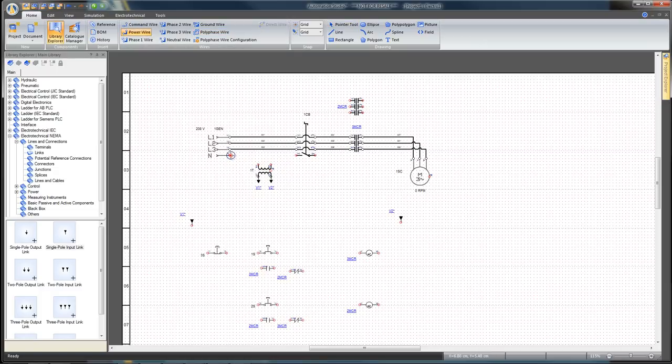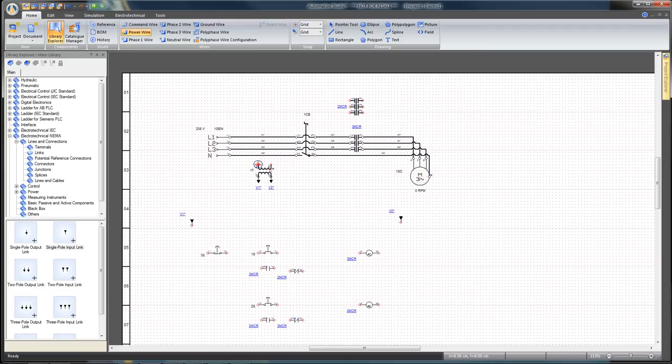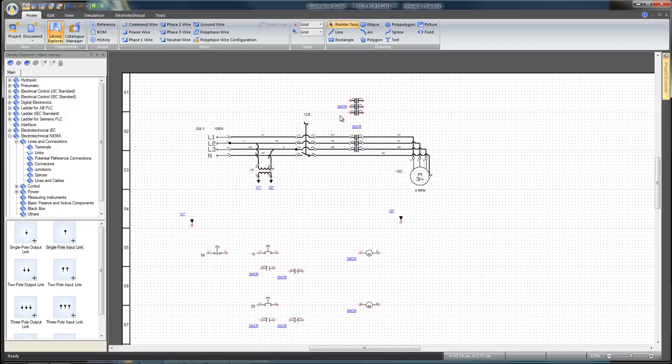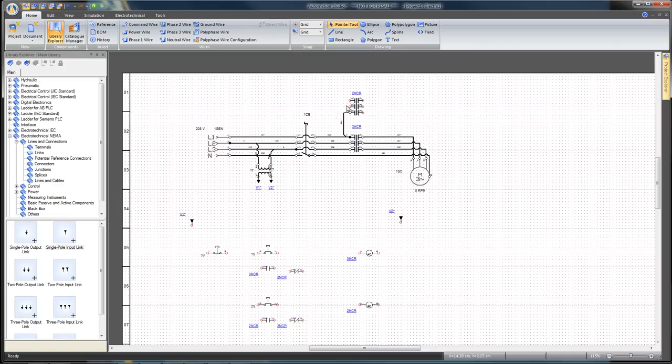Click on Power wire in the Home tab to select the one power wire. Connect the neutral from the three-phase source to the other neutrals. Connect the transformer to two different phases. And connect the other contact group from the circuit breaker to the motor. Make sure that two phases are inverted to permit reversing the motor rotation direction.